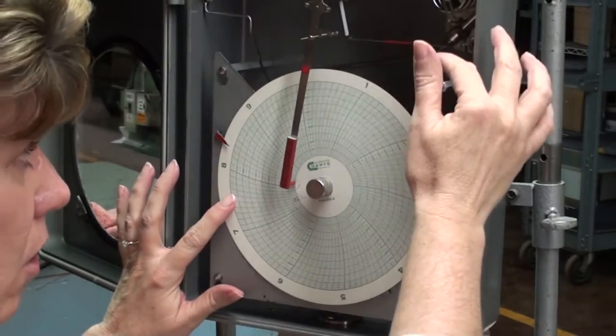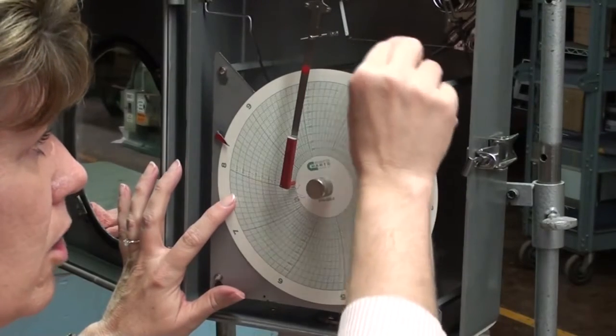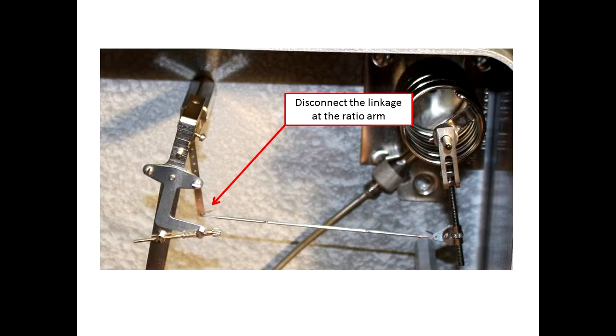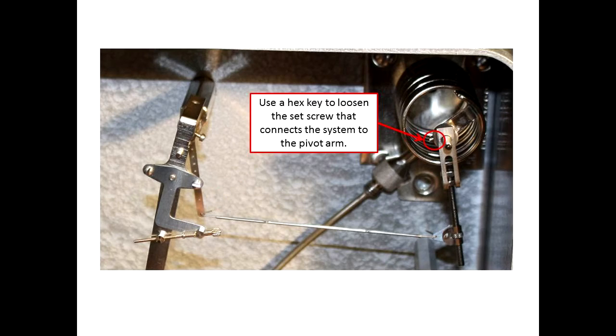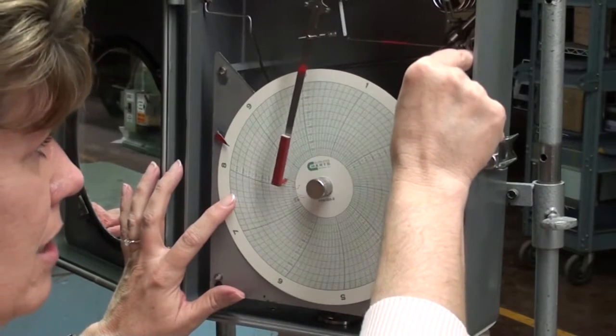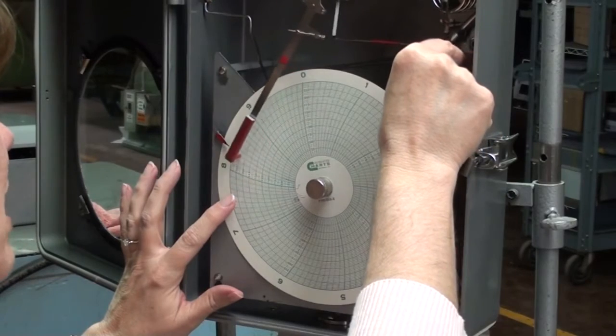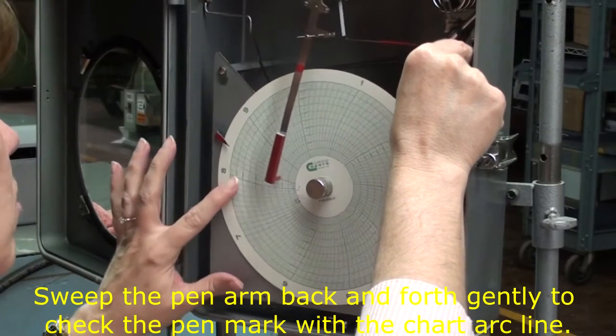And to check the arc line, you can do it two ways. You can take and disconnect your linkage here at the ratio arm, or you can loosen the set screw that attaches the adjust arm onto the pivot of the pressure system. Now, I've not tightened this yet, so mine is just a simple matter of swinging it back and forth.